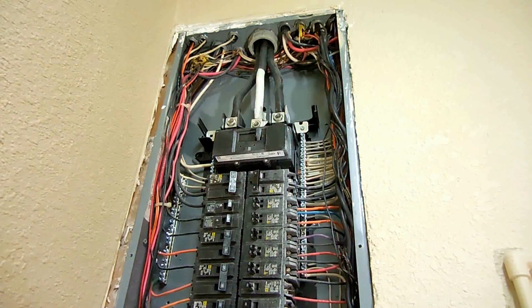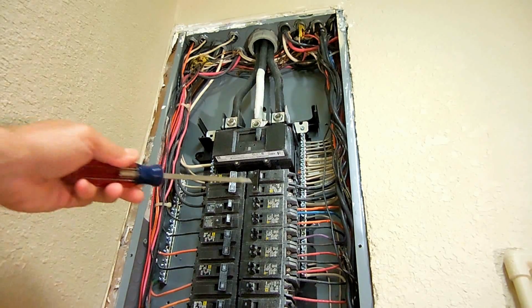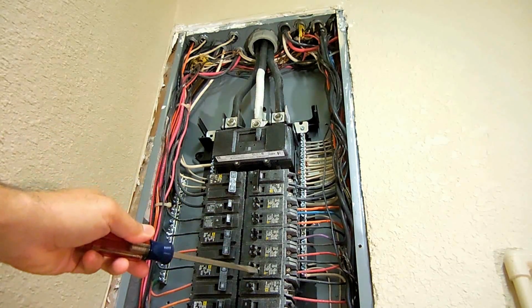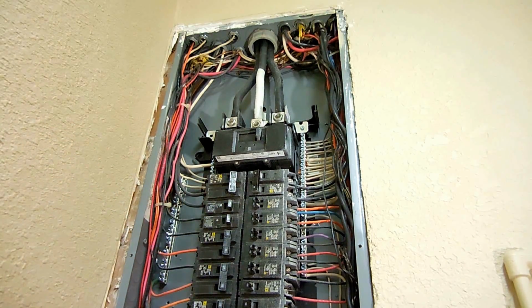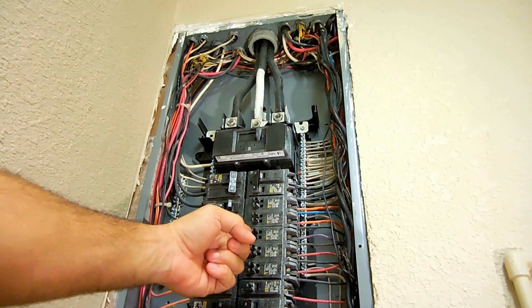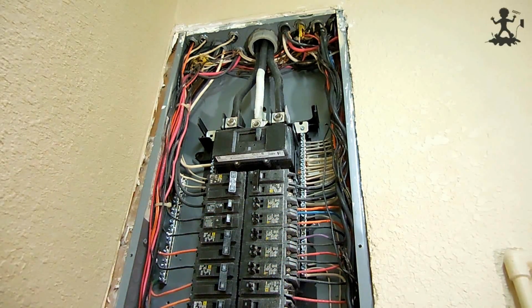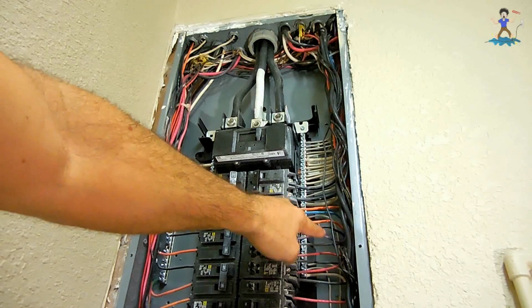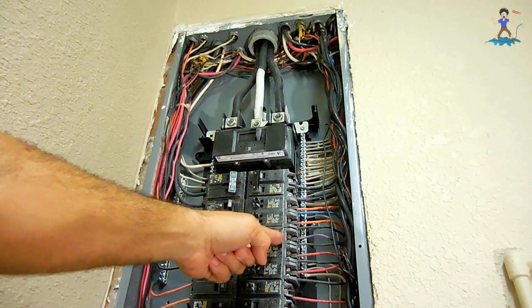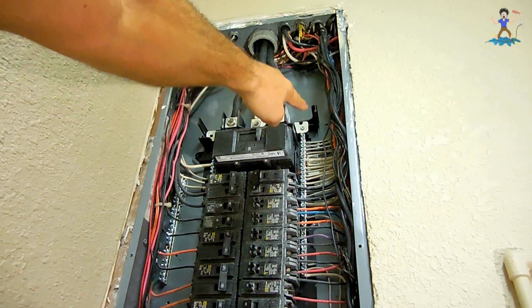If you're experiencing a problem where one of your circuit breakers is tripping intermittently, and you have removed all the loads from that branch circuit and it continues to do it once in a while, then what you're going to have to do is just make sure that breaker is in the off position. You're going to remove the wires connected to the circuit breaker, and you're also going to remove the neutral wire connected to that circuit from the neutral bus bar.